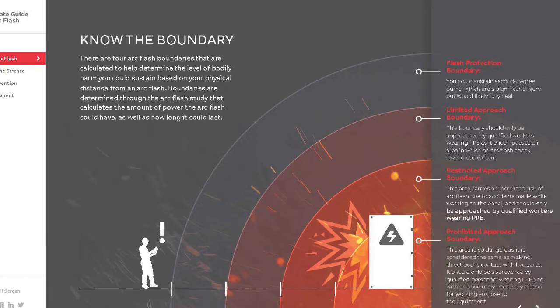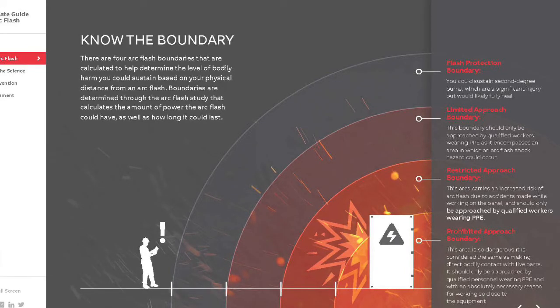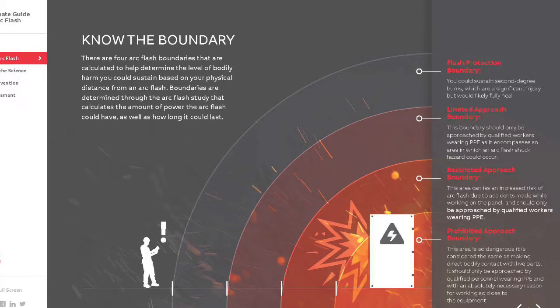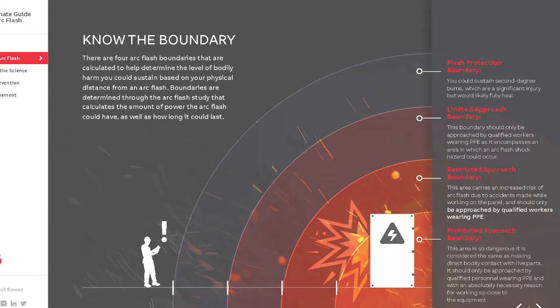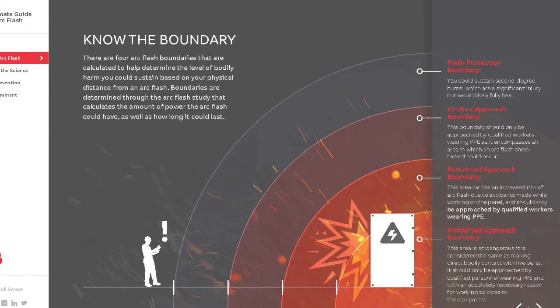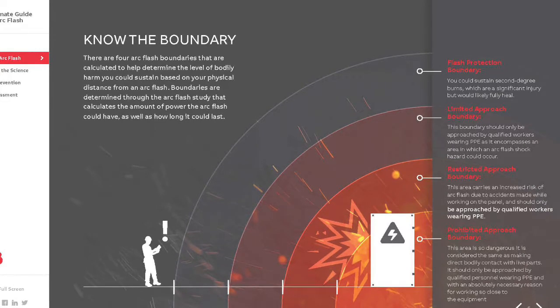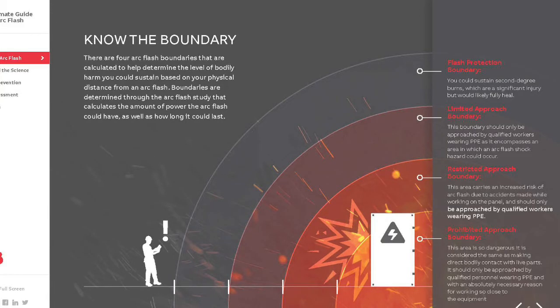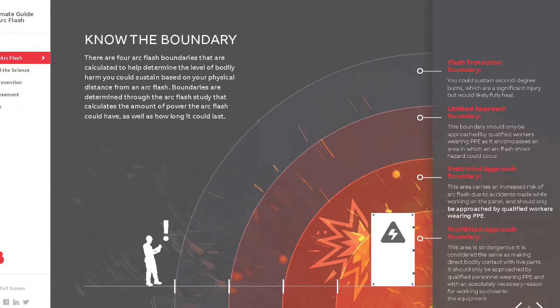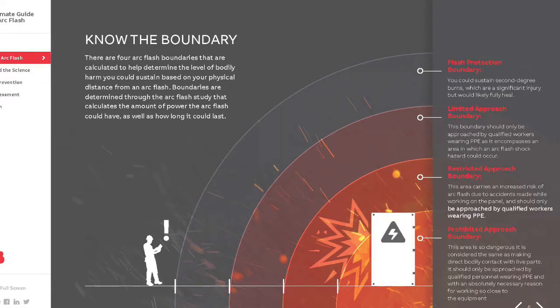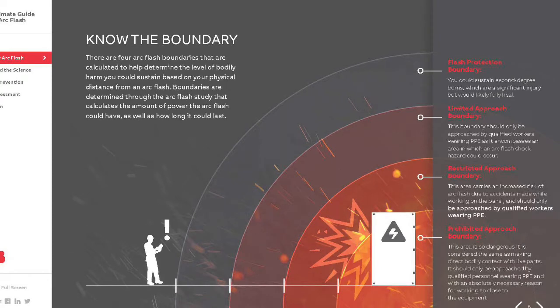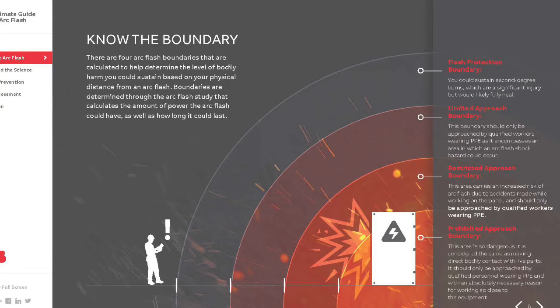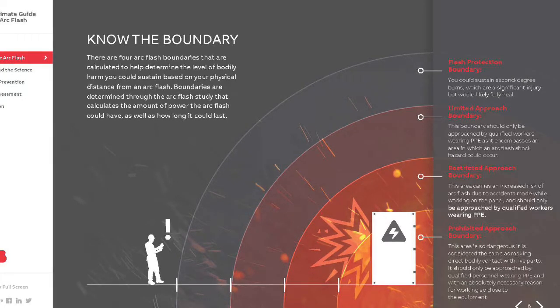The second boundary is the limited approach. This shock protection boundary is the approach limit for unqualified employees and is intended to eliminate the risk of contact with an exposed energized electrical conductor or circuit part. Unqualified persons are only allowed to enter this boundary if escorted by a qualified person. The third boundary is the restricted approach — this shock protection boundary is the approach limit for qualified employees.